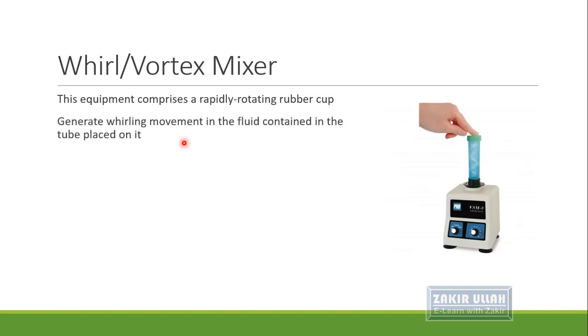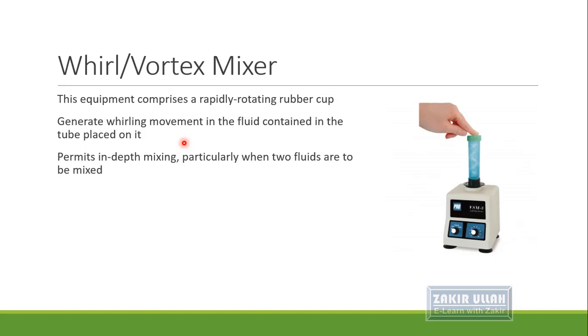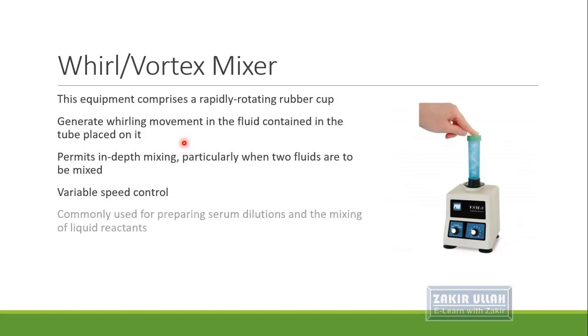The vortex mixer contains a rapidly rotating rubber cap or head. When a tube containing fluid is placed on this head, the vortex mixer produces a whirling motion and mixes the solution. This type of mixer allows very thorough and in-depth mixing, especially when two fluids are mixed with each other. The mixer has an adjustable speed range and is commonly used for preparing serum dilutions or dilutions of different solutions reacting with each other.